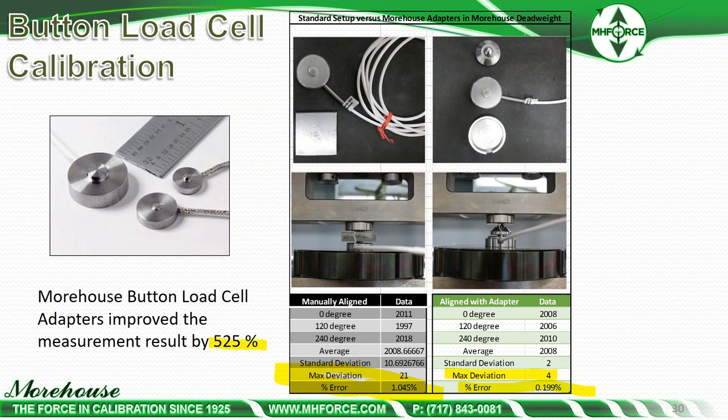People use button load cells and say the manufacturer claims 0.5% accuracy. Guess what — you're not going to get 0.5% on these things. 0.2% is very, very good for this type of cell. We're rotating it, introducing reproducibility errors, and getting 0.2% — that's about the best you're going to get. If you buy this cell expecting 0.5%, it's probably not going to happen.